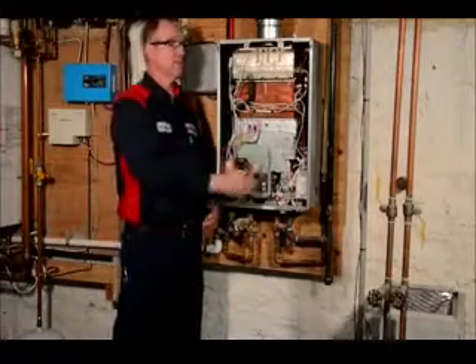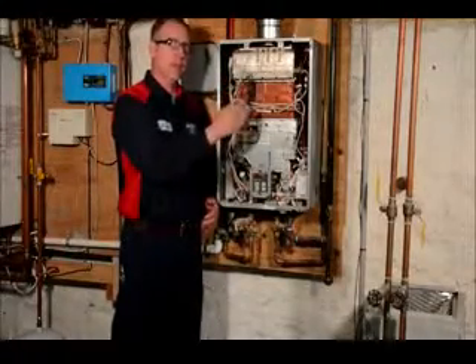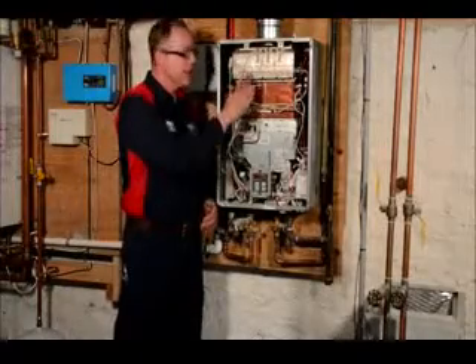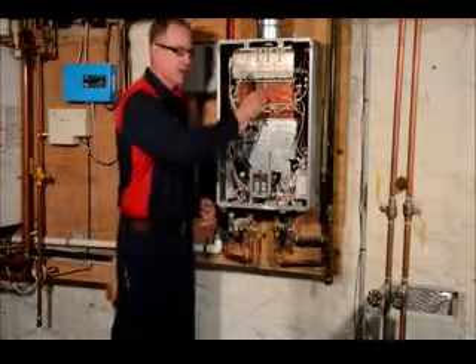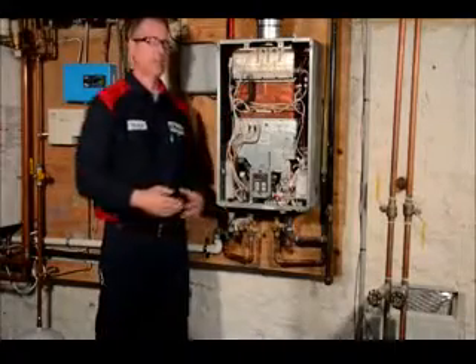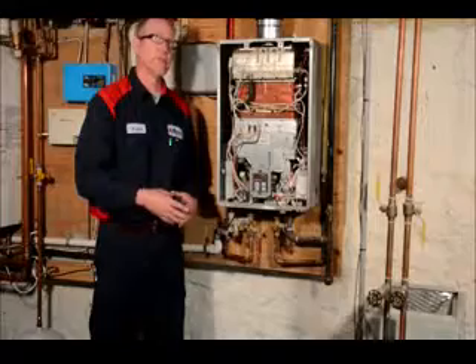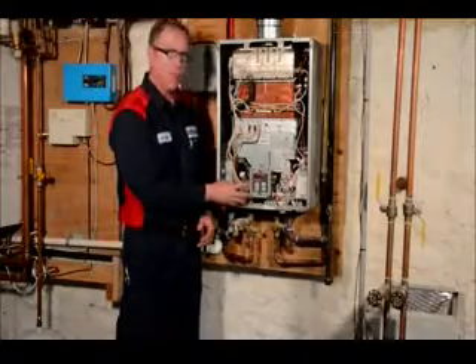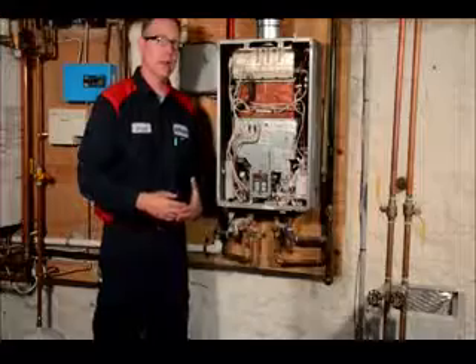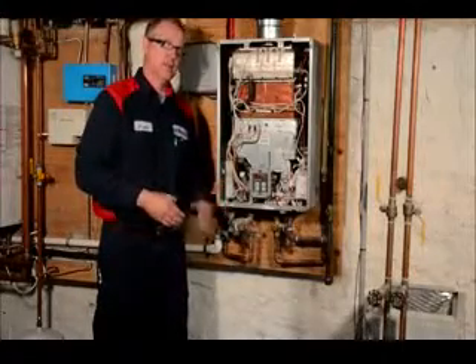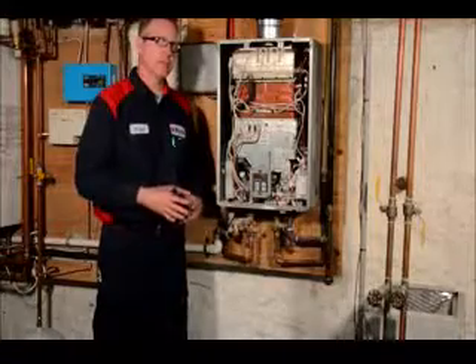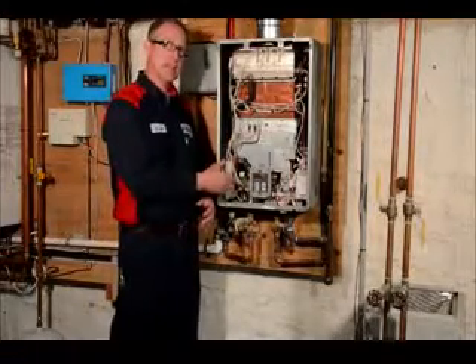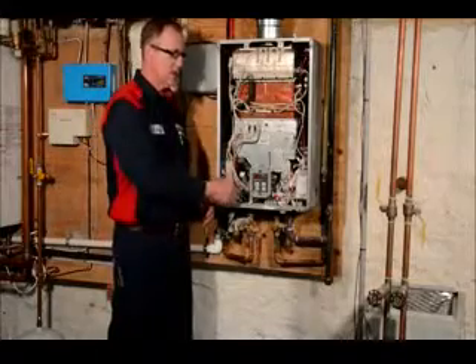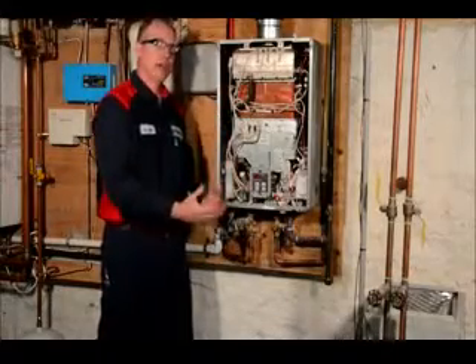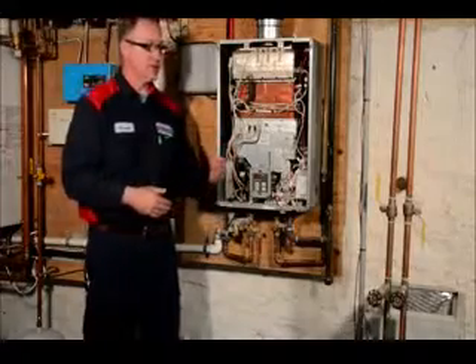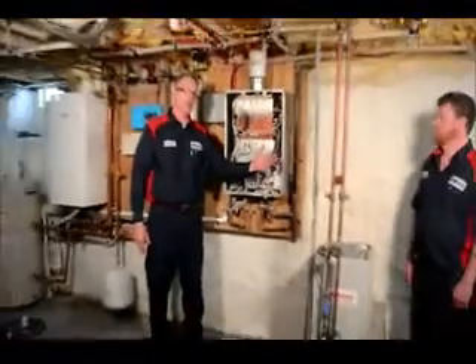It's taking the exhaust gases on the way out of the appliance, and the incoming water strikes this heat exchanger first. It then strikes our primary heat exchanger, and as it's leaving the tankless, it strikes another thermistor to monitor the outlet temperature. This is the control panel. We have this one set at 120. Rinnai will guarantee 118 as high as 122, so plus or minus 2 degrees. This has a modulating gas valve in it, and that's why it uses the flow sensor and the thermistors to get your high efficiency. And speaking of high efficiency, we'll send it on over to Corey to discuss the Rinnai hydronic furnace.